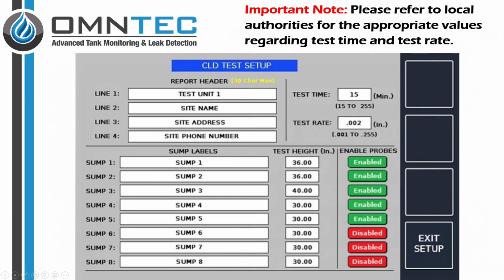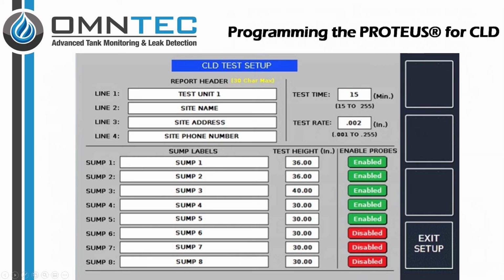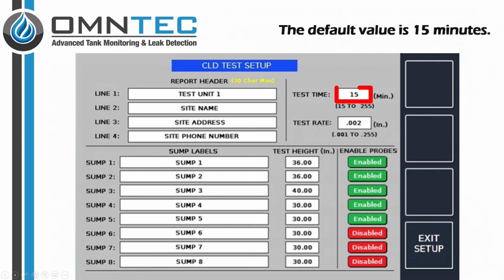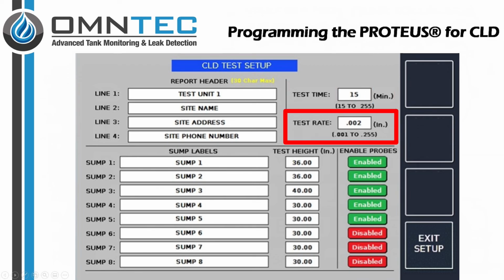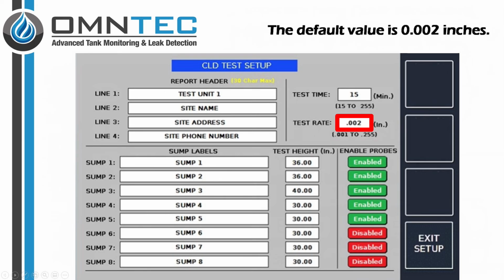Please be aware of an important note. Refer to local authorities for the appropriate values regarding test time and test rate. Select test time and enter the duration of the test. The default value is 15 minutes. Select test rate and enter the allowable change in height for the test. The default value is 0.002 inches.